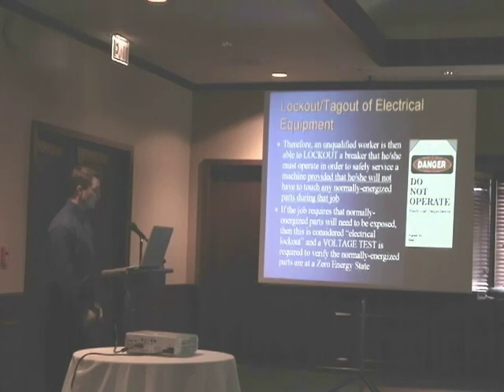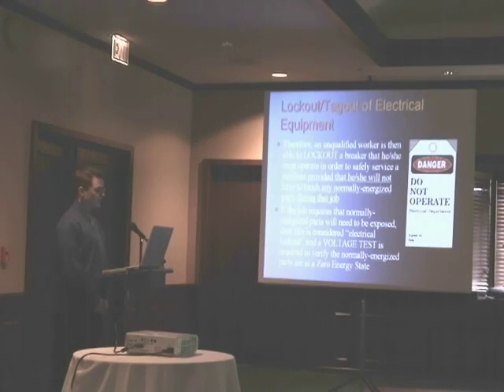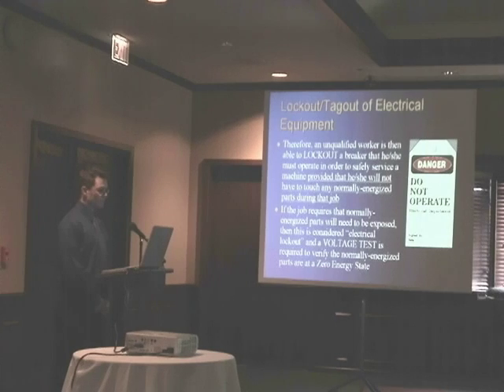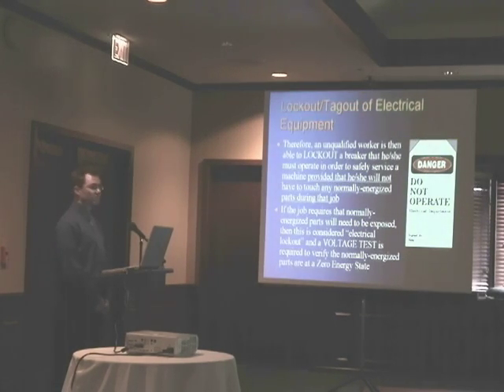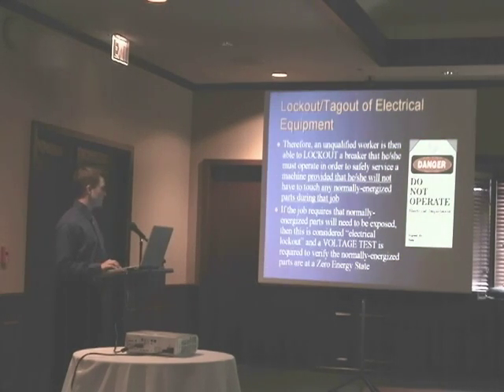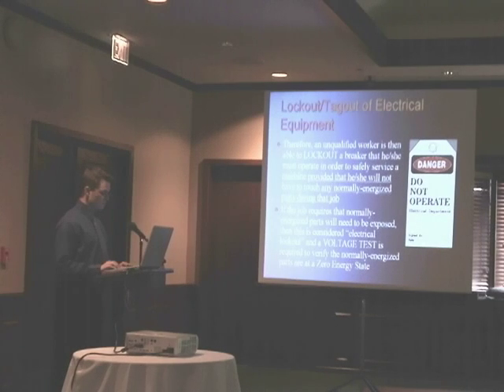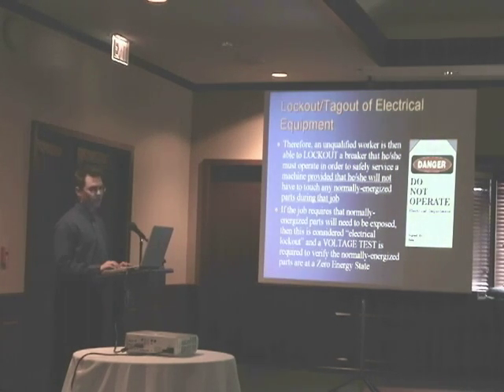Therefore, an unqualified worker is able to lock out a breaker that he or she must operate in order to safely service a machine, provided that he or she will not have to touch any normally energized parts during that job. If the job requires that normally energized parts be exposed, this is considered electrical lockout, and a voltage test is required to verify that they're at the zero energy state.